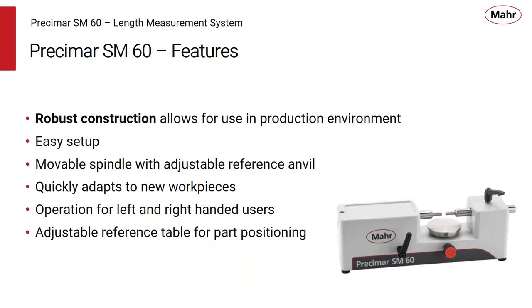What are some of the features of the SM60? Well, with any precision length measuring system, you need to have something that's robust, stable, and really made to measure down to parts of micro inches. And that's what the Precimar SM60 is. It's a robust construction that's really made to measure to very tight tolerances. What's nice about it is that it's easy to set up. So you can see it has simple handles on it here to control the reference spindle and to retract the sensitive spindle, so you can adjust it to a lot of different sizes. It quickly adapts to new work pieces.